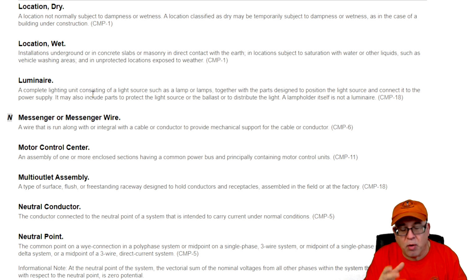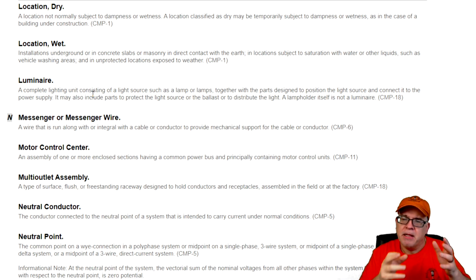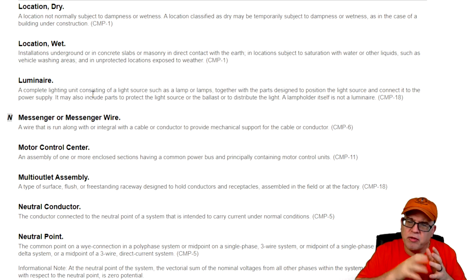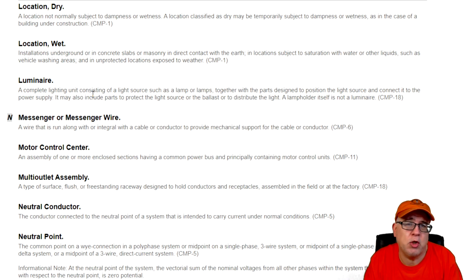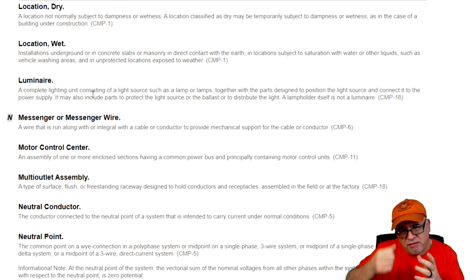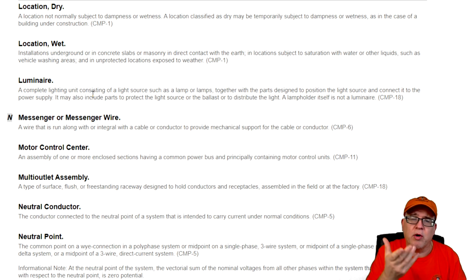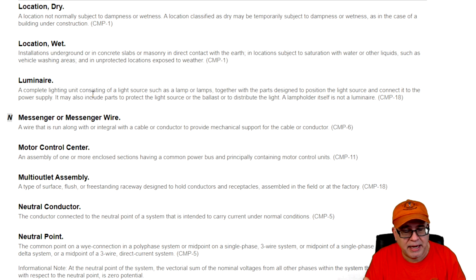Just a light bulb is a lamp, it's the accurate name for it, even though Thomas Edison will be rolling in his grave. It is a lamp, and when you just do that, it's plugged into a lamp holder. Now, that's not to confuse a luminaire that might have an exposed lamp. A lamp holder is very specific. I'm sure you all have seen it. We refer to them many times as keyless. It's basically a porcelain or plastic base that the lamp screws into. Some of them have a pull chain on it, some do not. And it goes on a lighting outlet. That is called a lamp holder. That is not a luminaire.